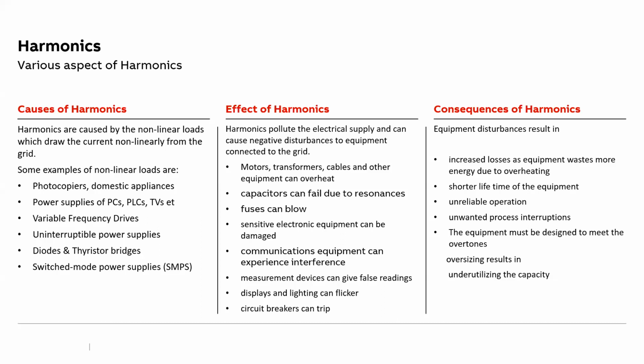Now typically, if we talk about a VFD, the harmonics generated are easily above 60 to 70%. Sorry, more than 70 to 80%. So for example, if a VFD is rated for say 100 amperes, and no mitigation technique is applied on it, then it would be consuming the normal 100 amperes plus an additional 70 to 80% of harmonic current. So the total current running through the system would easily be 160 or 170 amperes. Whereas if my system has been designed for 100 amperes, and harmonics have not been taken into consideration, then obviously overheating will occur. My cables will get overheated, and over a period of time it might even burn your installation, and a short circuit might occur. We have seen in many places we hear about fire, and the most common reason for fire is short circuit. So this could be one of the reasons.